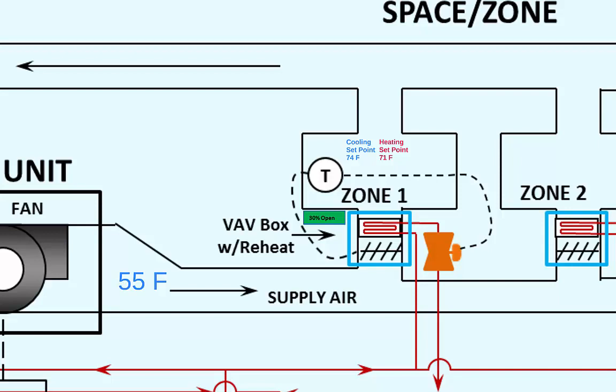Thus, the controller will lock the damper at minimum position, and now start to modulate the reheat valve open. From that point forward, the reheat valve will modulate to maintain the heating set point in the space. If a bunch of people return to the room, the temperature may again start to rise above 71 degrees Fahrenheit. The reheat valve will modulate towards a closed position in order to maintain that 71 degrees set point.